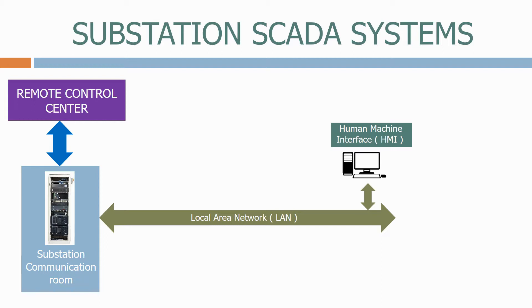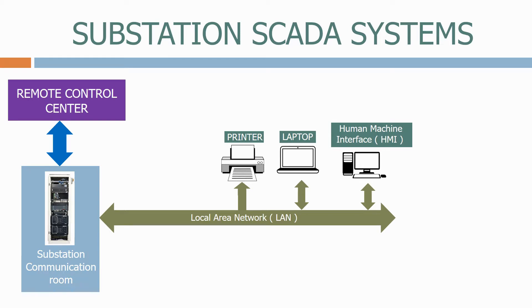We then have additional equipment such as laptops and printers. It's really important for the SCADA system that all the events and alarms are time-stamped so that we know exactly when they happened. To do this we normally have a GPS time-synced switch to which all the protection and control equipment is synchronised.